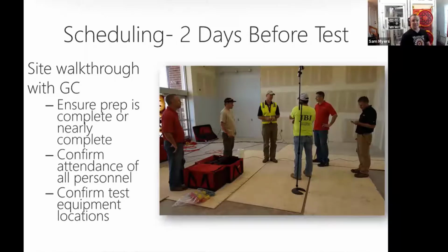Sometimes things on paper don't quite work out like they do when you actually walk the site. So you want to make sure the test setup plan you made from the building plans is actually going to work in reality. Go see those doors with your own eyes where you'll set up the fans, look at the area where you'll set your laptop. If it's multi-floor, you'll want to run reference tubes up to make sure the whole building reaches your desired test pressure.